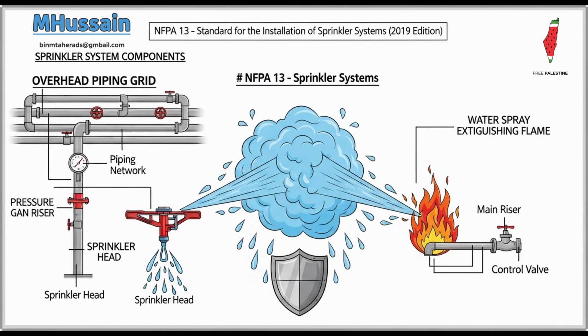Okay, speaking of suppression, let's get to the most fundamental requirement of all: the water supply. Where must the water come from, and what actually constitutes a reliable source? Yeah, the standard is very specific here. Acceptable sources include, first, a reliable waterworks system, and the volume and pressure there have to be determined by current flow test data or some other approved method. Second, a single automatically controlled fire pump that's installed in compliance with NFPA 20, the pump standard. Or third, a pressure tank installed according to NFPA 22, the tank standard. The emphasis is always, always on proven pressure and guaranteed volume for the required duration.